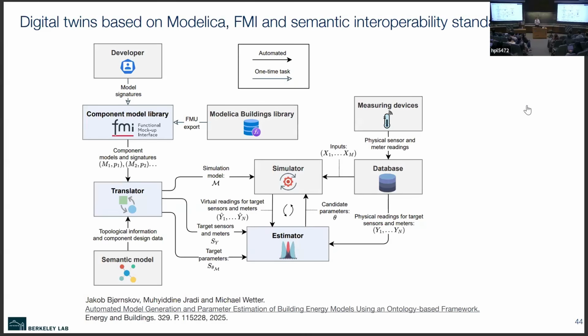A database that's fed with measurement devices from the actual buildings, and then using estimation methods, we can identify parameters and look, for example, at parameter drifts, using that as part of a fault detection and diagnostic method.